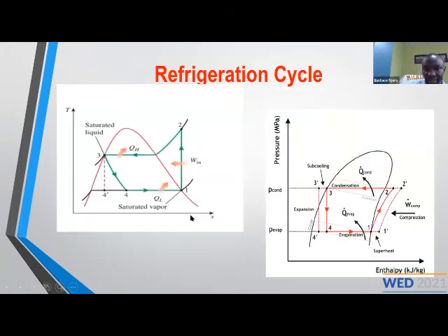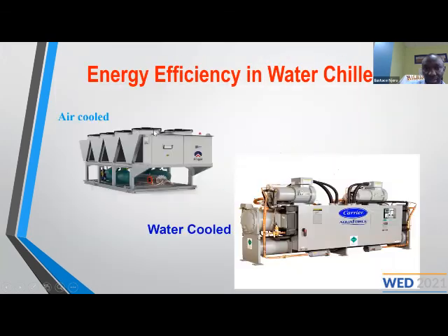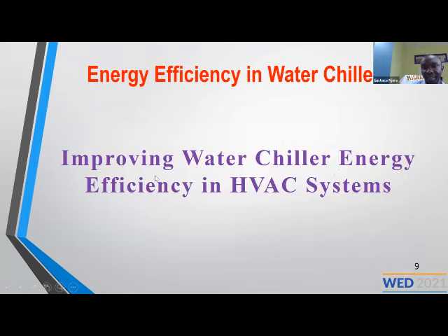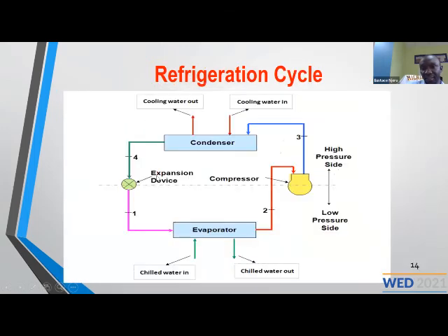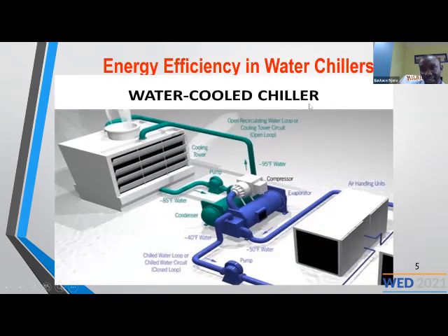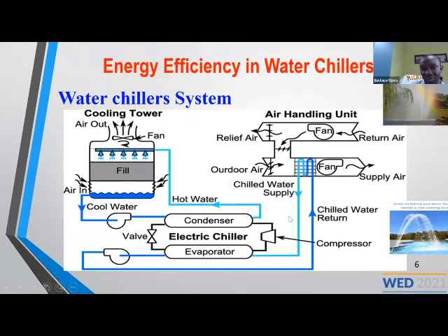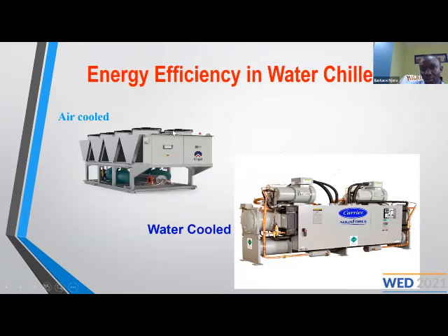The other one is air-cooled chillers. You need to check the fans. You can see these air-cooled chillers. Here you have fans, and in most cases in most chillers these fans are running throughout. So you need to get fans whose spin you can reduce, or you can switch off some fans depending on the cooling load. You see, in your refrigeration cycle, if the load in the air handling units is not much, you need to be able to switch off some fans to avoid overcooling the refrigerant for no use.